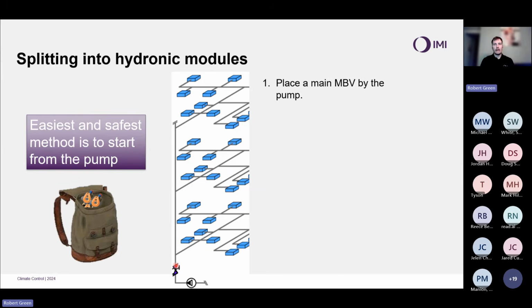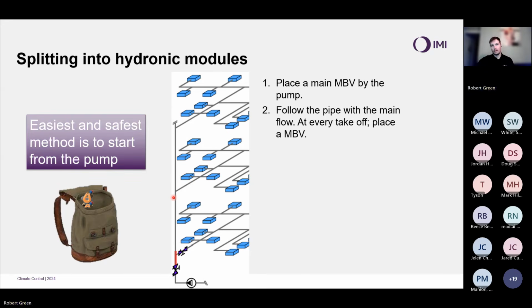What we then do is we follow the path of the main flow in the system. And as we can see here, the main flow is going to carry on up the system. At every takeoff, anywhere where the main flow is not going, we place a manual balancing valve. So we place a manual balancing valve on the floor here, and finally at the end here.